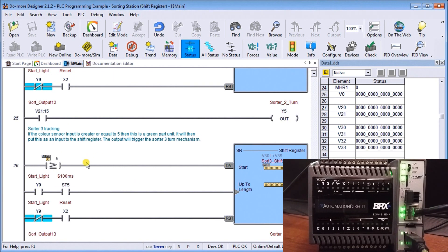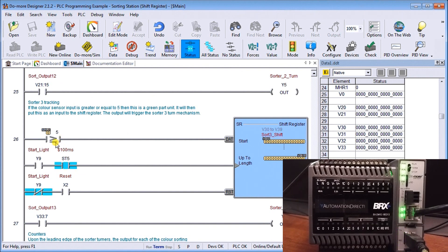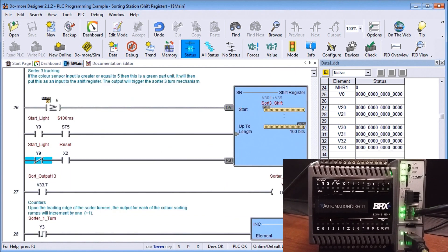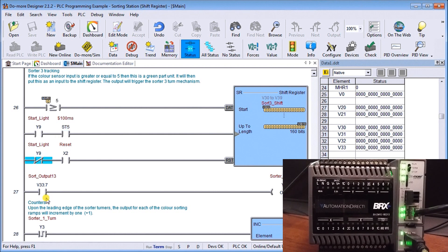Then we have V21:15, which is the second register word in our shift register and the 15th bit. When that comes on, it turns on our sorter number two, which diverts that product over. Number three has to be our color sensor greater than or equal to five, so either five or six, which is a green color. We throw that into the shift register, and our output is from V33 and the seventh bit. As we go along the conveyor belt, we need further distances before we do the reject or the sorting.